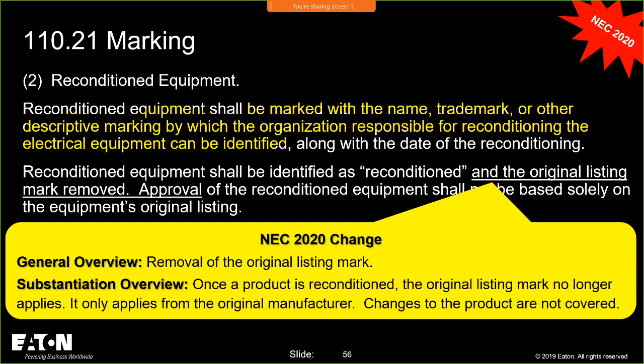that original listing mark is no longer valid. It was only valid from the original manufacturer when it's shipped from the plant. The moment it gets out there in the field and starts to get living experience, it's not really giving you the value anymore. And what you don't want to do is do refurbishing and reconditioning and leave that mark on it, and then the end user thinks it's a UL listed product that got a third party review after you did your change and your magic on it.